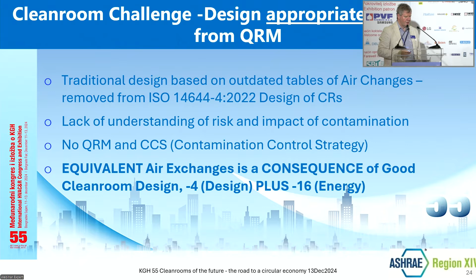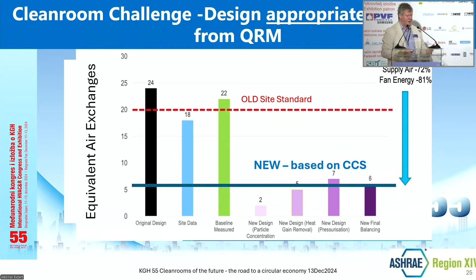one of the things we talk about now is getting to equivalent air change rates. But here's an example of a table showing you different aspects of part of an example of a clean room. And all I need you to look at there is that you have the old site standard and the standard based on contamination control strategy or the removal effectiveness. And you're looking at vast increases in energy reduction efficiencies. Okay, so you're looking at dropping the air volumes by three quarters. Traditionally, we over-design, so we need to change how we design with less air, but the air needs to be focused in a better area within that, right?